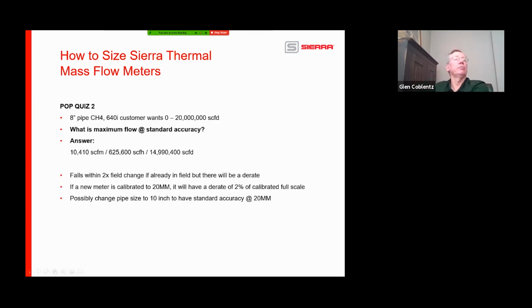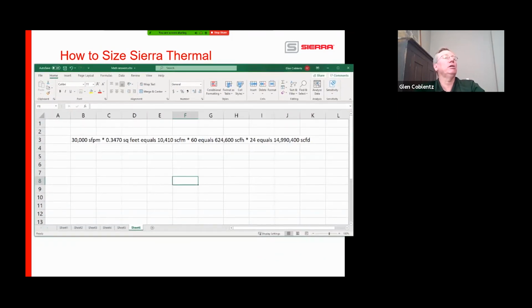So here's the answer. Answer, 10,410 SCFM, 62,500, which is an error. This should be 64,600. And 14,990,400 standard cubic feet per day. How in the world did we figure that out? It's right here. 640i, standard accuracy, 30,000. There's your square feet. There's your SCFM. Times 60 to get to hour is 624,600, times 24 gives standard cubic feet per day.